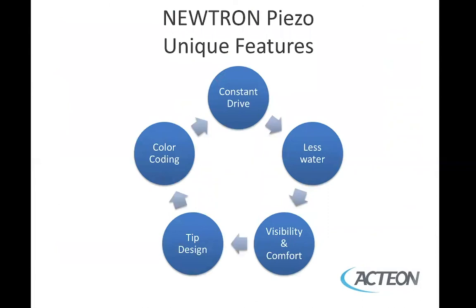The Newtron has features unique to piezo, particularly the constant drive — like cruise control on your car — so even when you engage a piece of calculus it won't back off. It also requires 50 percent less water than a Cavitron, helping with visibility and patient comfort. There are over 80 tips to select from for various treatments including scaling, endo, and minimally invasive restorative dentistry. Each tip is color-coded to indicate the maximum power level for that tip.